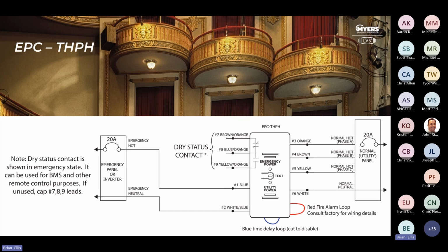One of which, just to scratch the surface, is that there's a lot of wireless stuff out there right now where they're sending a heartbeat to your emergency controls. And then what it's looking for is loss of power on the normal, like, let's say the controller. Whenever those devices see that loss of power, they lock on. So we can actually utilize this device to monitor all three phases of normal, and then we can send or open the contact so that that device fails. So again, lots of solutions here in our bag of tricks.